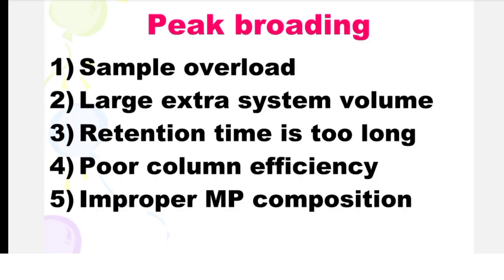Number one is peak broadening. Peak broadening is due to sample overload, large extra system volume, retention time is too long, poor column efficiency, and improper mobile phase composition.